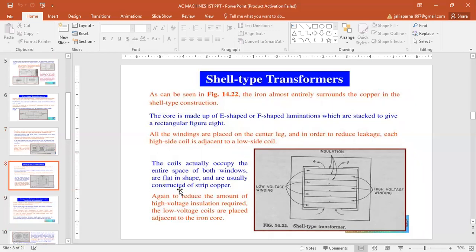As can be seen in the figure, the iron almost entirely surrounds the copper in the shell type transformer construction. The core is made up of E-shaped or F-shaped laminations, which are stacked to give the rectangular figure 8. All the windings are placed on the center leg, and in order to reduce leakage, each high side coil is adjacent to a low side coil.